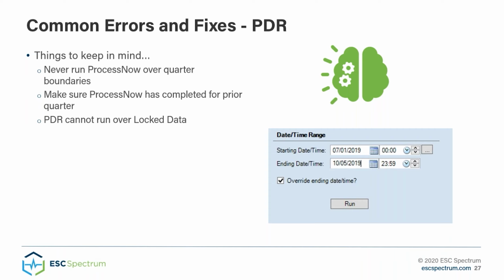So using the history report, you could go back and find, hey, did we pass? So, we've got the fourth quarter is going to start here very soon. When it does start, if you were to fail ProcessNow specifically on the PDR task, you'd want to go back into the third quarter, back into September or October 1st. That's the actual last day that the third quarter ProcessNow sequence would run, and make sure that one's passing before trying to keep going and troubleshooting rerunning for fourth quarter.